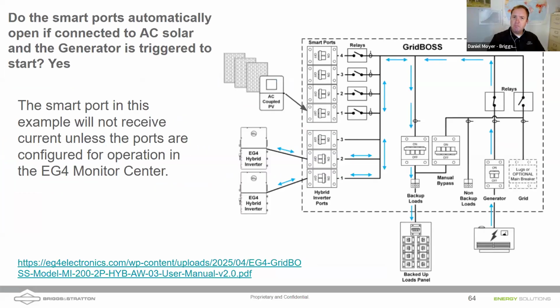Another reason I really like the Grid Boss for generator integration is when we have AC coupled solar. I mentioned earlier that we use a microgrid formed by the inverters powering into the Grid Boss to create a microgrid, and we can use frequency adjustment. One issue you get, though, is when the grid is present, the inverters become grid following, which isn't a problem because AC coupled solar can be backfed to the grid. But when we start up a generator, the inverters become grid following as well. The inverters aren't grid forming anymore. So when we have AC coupled solar and we are running a generator, we lose the ability to curtail AC coupled solar using frequency adjustment.